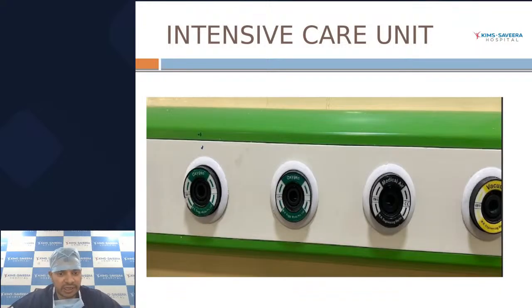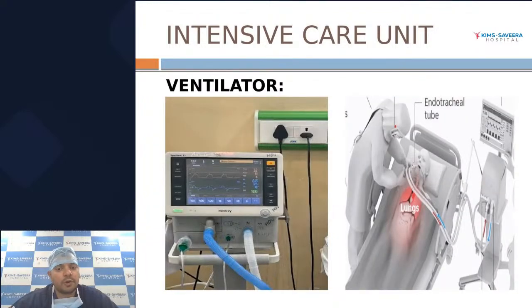These are usually the ports that supply the oxygen. In highly advanced centers, we keep a standby oxygen port most of the time. Ideally there should be three ports, one for oxygen, one for medical air, which is compressed air, and the third one is vacuum. Vacuum is used for suctioning all the secretions that are regularly produced. Once you put the patient on the ventilator, he doesn't have the reflex to swallow or spit out his secretions. In such a case, you use vacuum suction. You pass a suction catheter through the endotracheal tube that is put in the mouth, and through that you suck out the secretions. This is how the mechanism works.